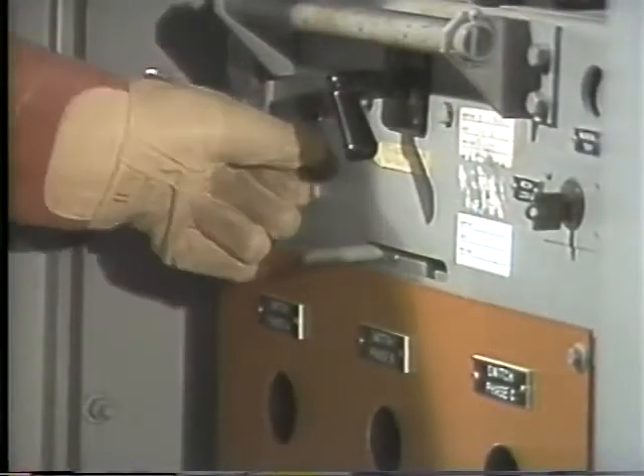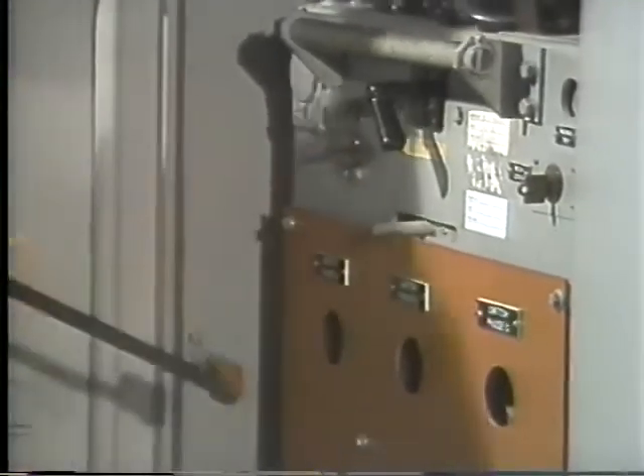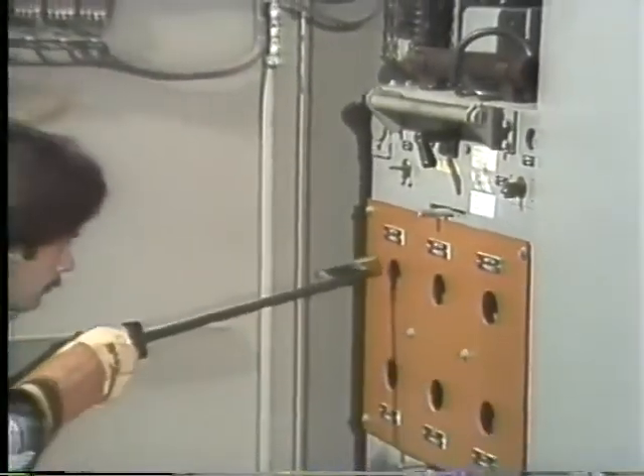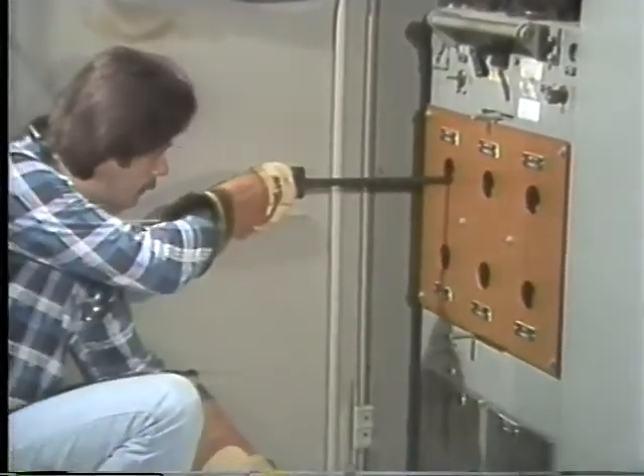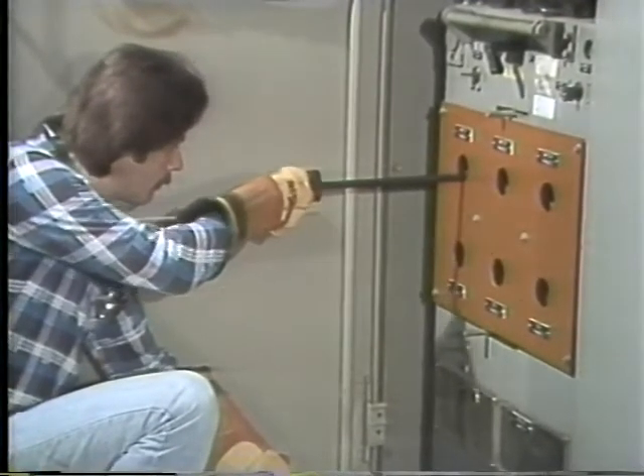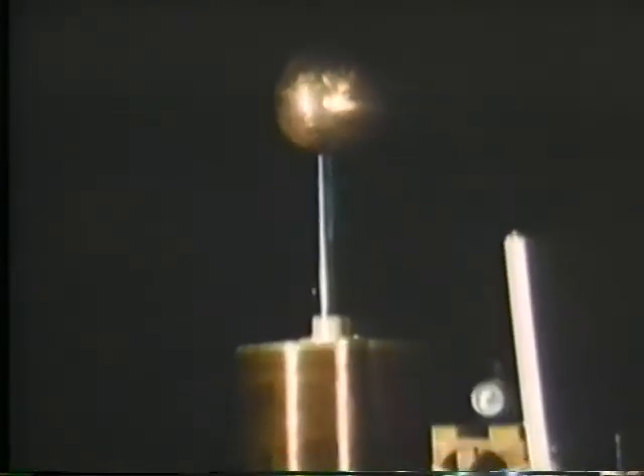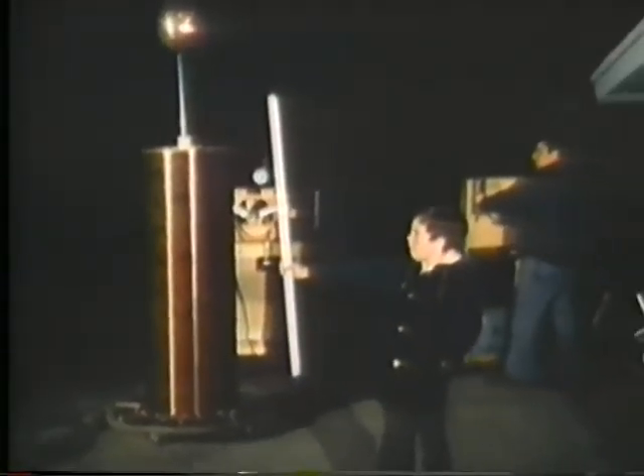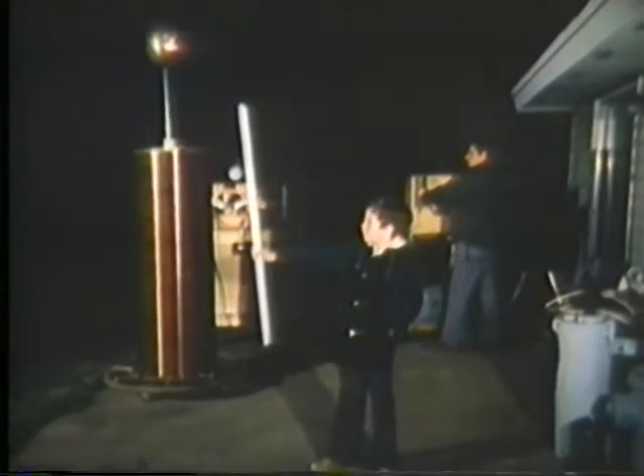In this section, you'll see some of the techniques and precautions used for working on high voltage equipment and learn about some of the not so obvious hazards that high voltage can present. Let's start with an experiment using a high voltage coil. The coil's de-energized right now, no current is flowing. Several feet away, there's a person holding an ordinary fluorescent tube. The tube's disconnected. No wires are attached. Watch what happens when we energize the coil.